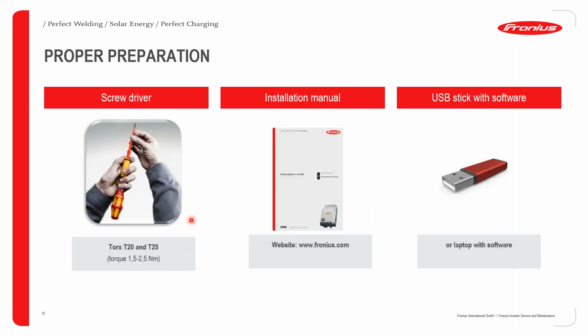So what do we need for proper inverter installation preparation? We basically need a screwdriver, like I mentioned earlier, the installation manual, and a USB stick, if you have to do a software update. And we recommend a screwdriver that has an adjustable torque, and the recommended torque is 1.5 to 2.5 Newton meter.